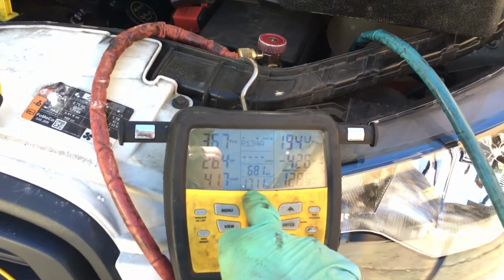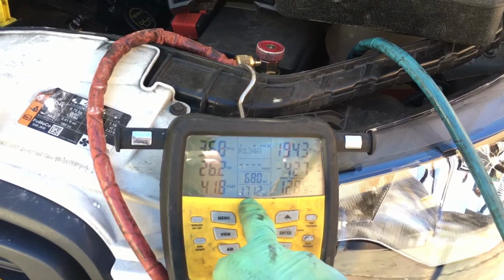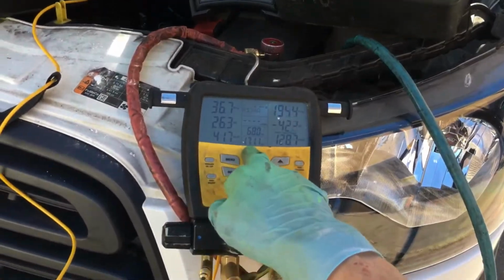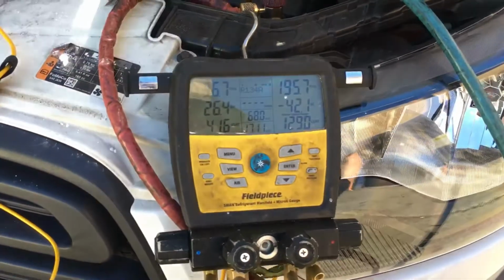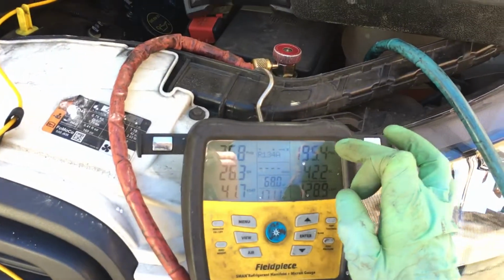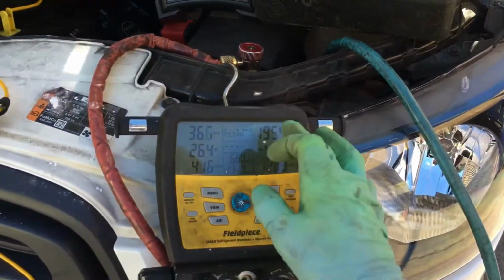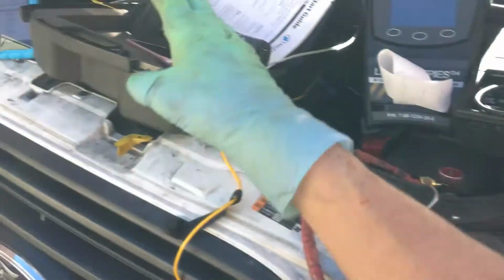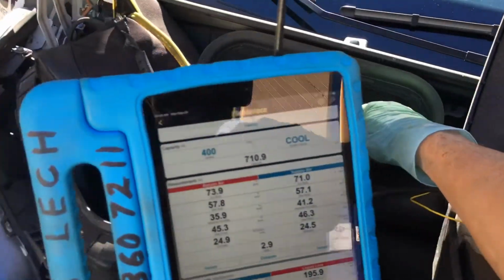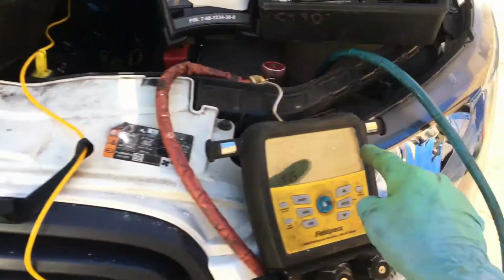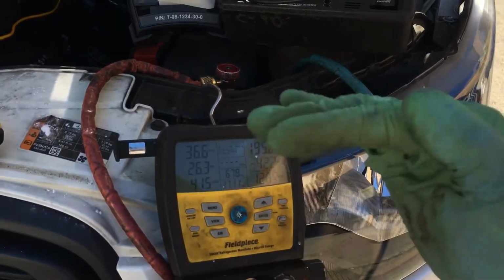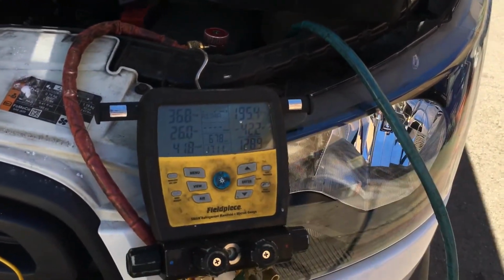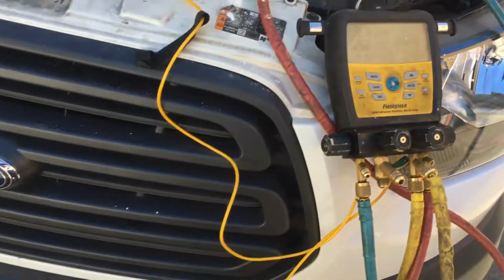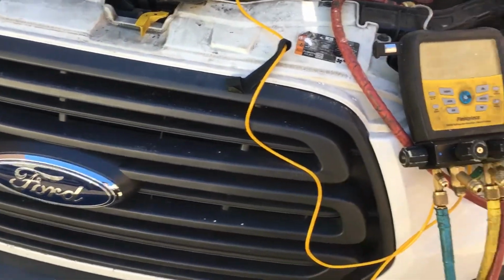Discharge temperature from the compressor is 171. It dropped a few degrees because we're not pulling over that load right there. So the high side pressure barely changed, a few psi. From taking in 115 degrees going across the evaporator to 72, 73 degrees going across the evaporator, the high side pressure is dead on right where it was, basically within a few psi. How could that be? Take this to residential HVAC.